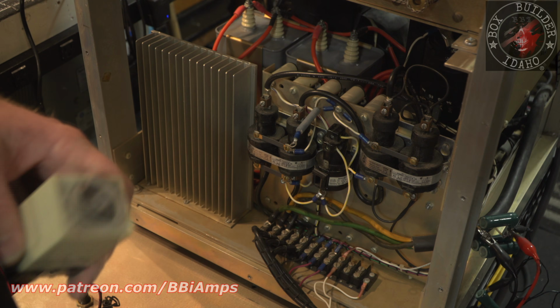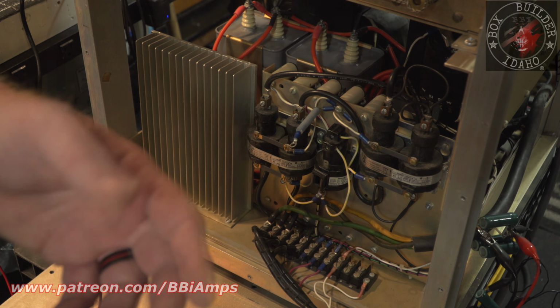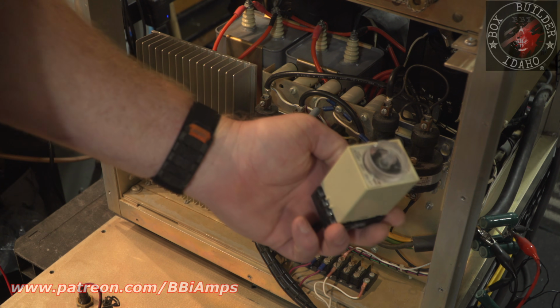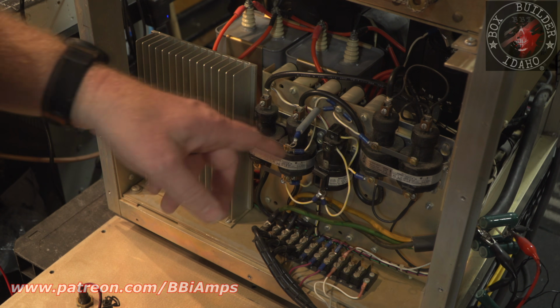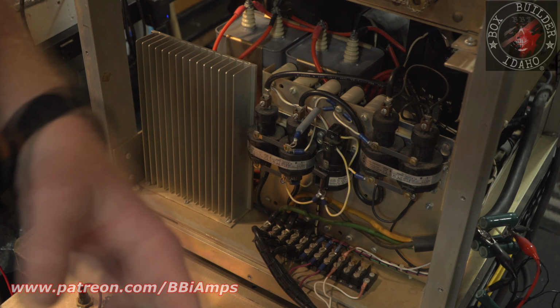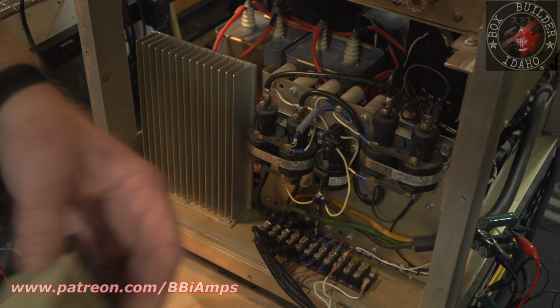The problem with that is if we have a short or anything that arcs over in the RF deck or in the high voltage supply, it can run back and wipe the contactor out. That's why we'd use this second one to trip it independently, and this would not be in the positive circuit at all for anything.